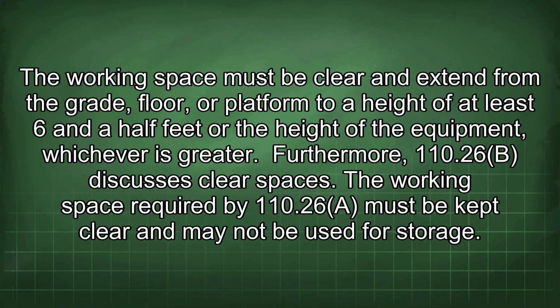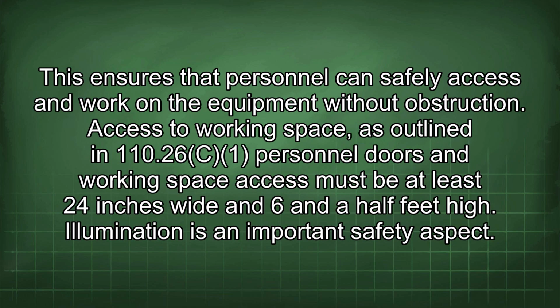Furthermore, 110.26(B) discusses clear spaces. The working space required by 110.26(A) must be kept clear and may not be used for storage. This ensures that personnel can safely access and work on the equipment without obstruction. Access to working space, as outlined in 110.26(C)(1) personnel doors and working space access must be at least 24 inches wide and 6.5 feet high.